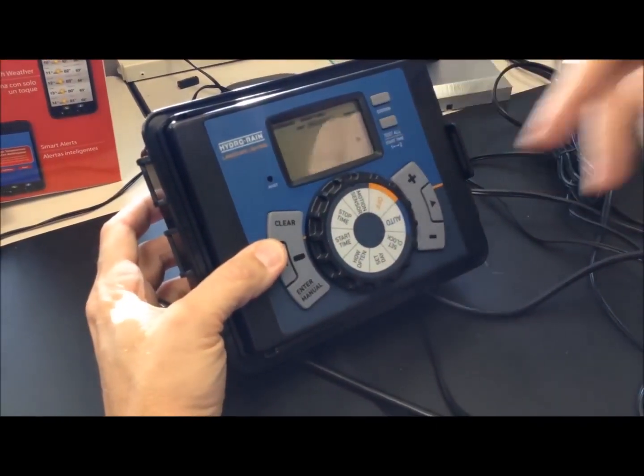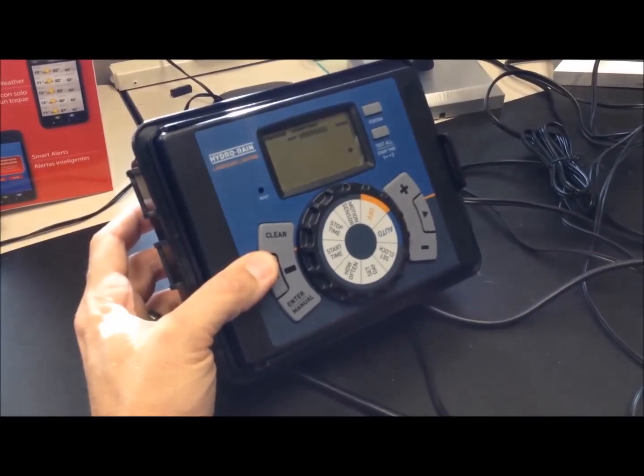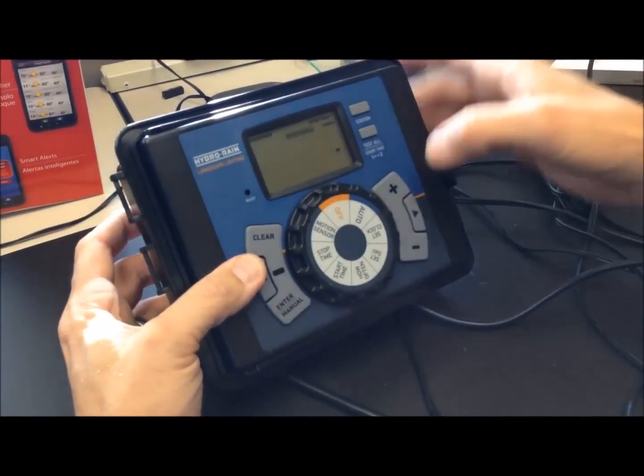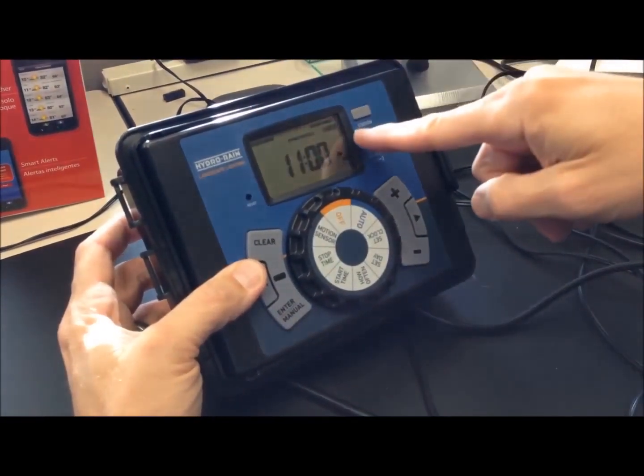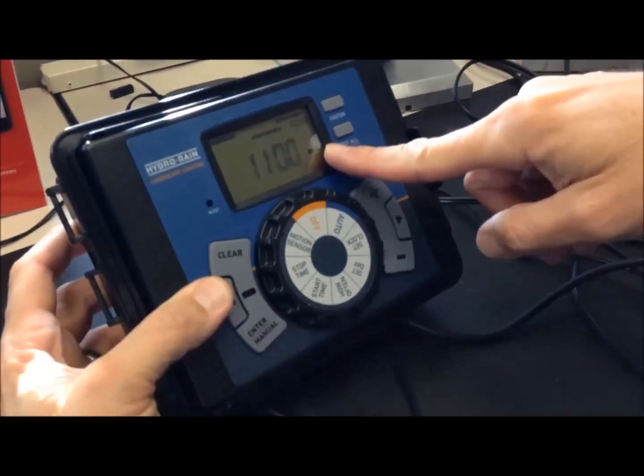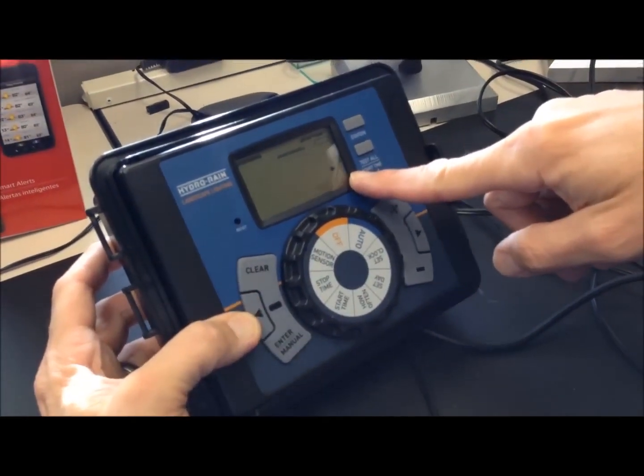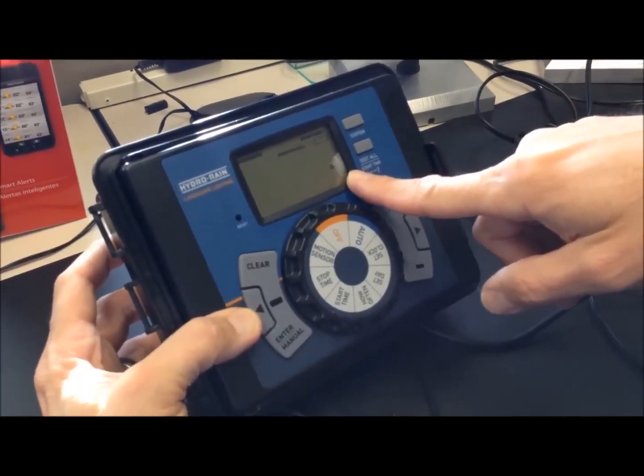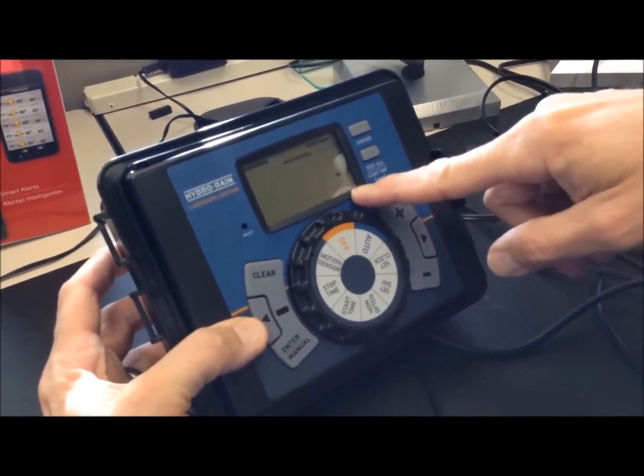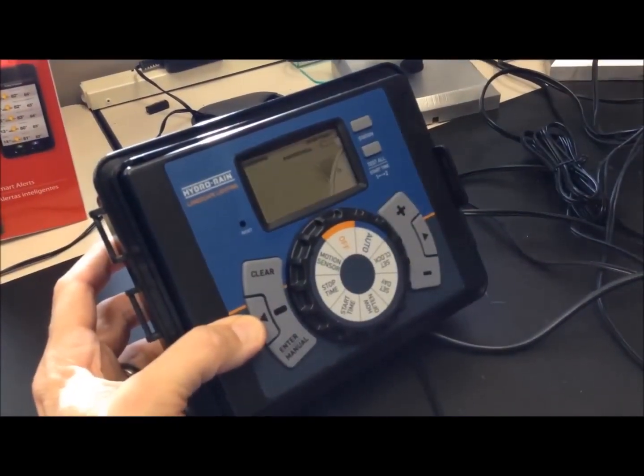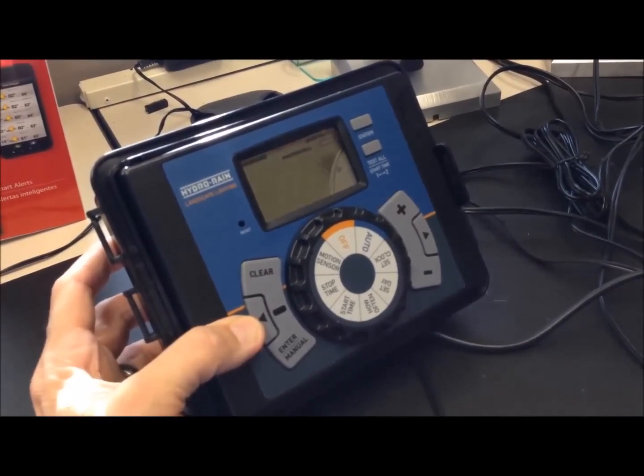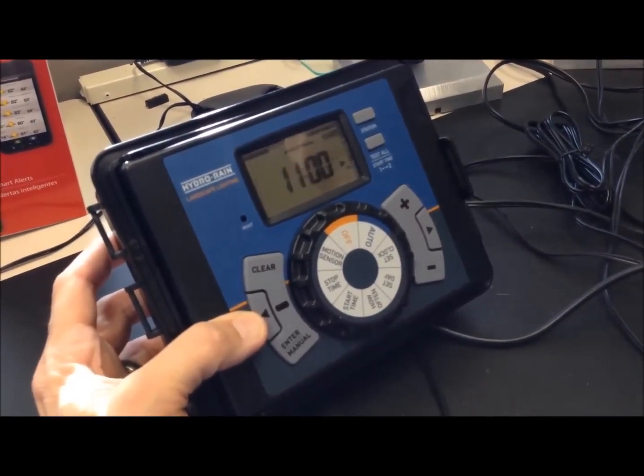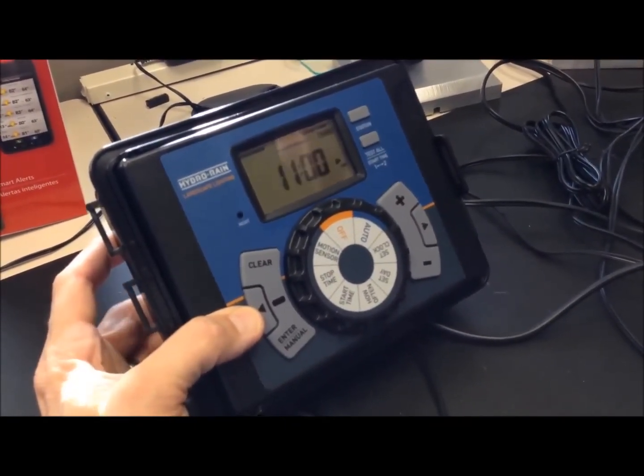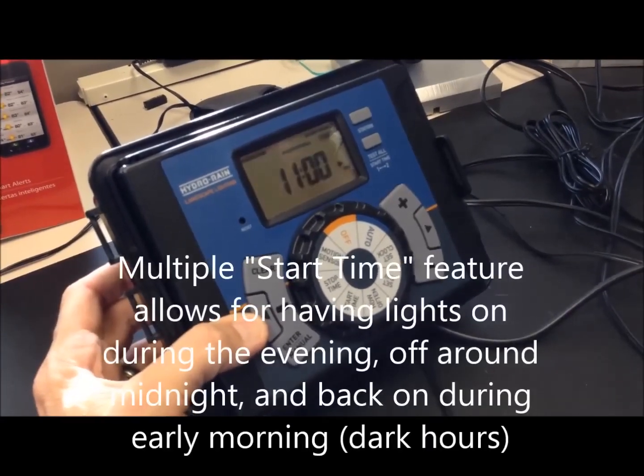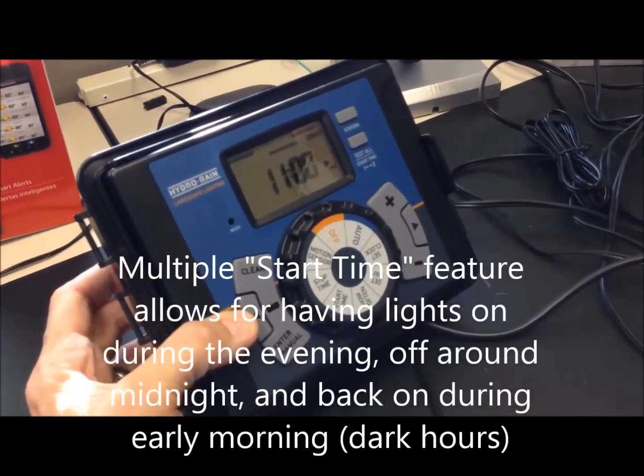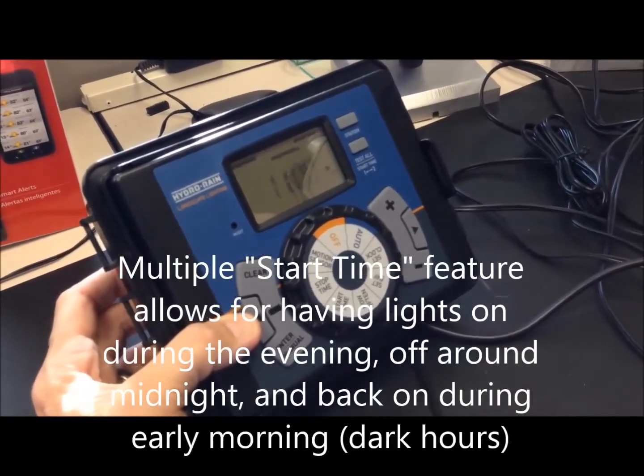You can use the photocell to bring your lights on, and then you can go to a stop time and have an actual time set for the stop time. The advantage of this is that now you can use your second start time. Instead of having your lights run all night long, they come on in the evening when people can see them, then they go off late at night, and then you can have them come on again in the morning if you'd like, so that you have light if you leave early in the morning.